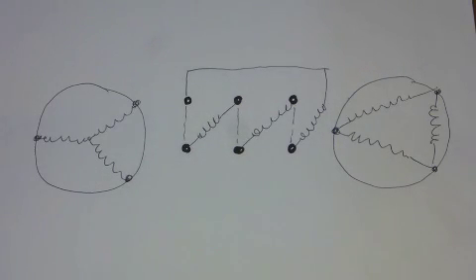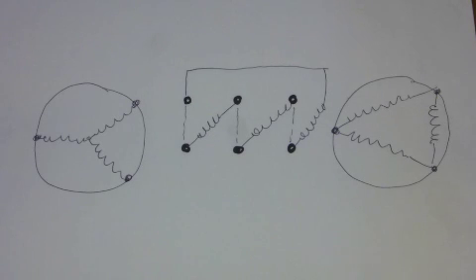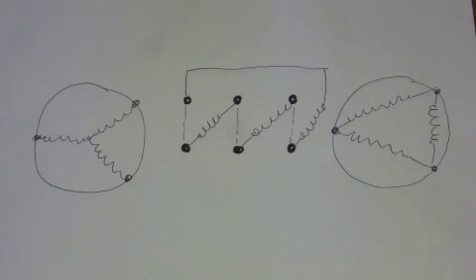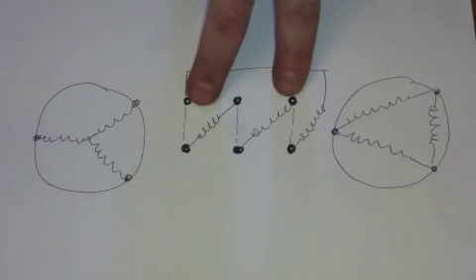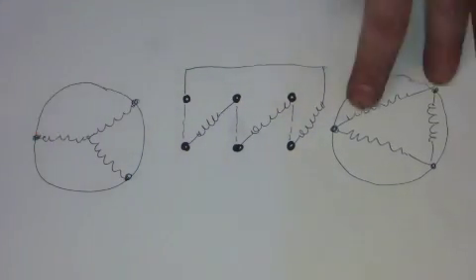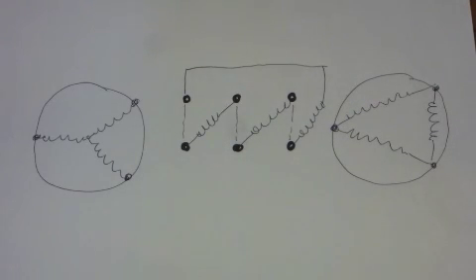A lot of the three phase conversions out there require your machines to have a dual voltage motor. You'll start to see diagrams like this and people talking about star and delta and you can alter the connections inside your motor terminal block to change the motor from star to delta in order that the motor can run on a three phase supply but a three phase supply of a reduced voltage.